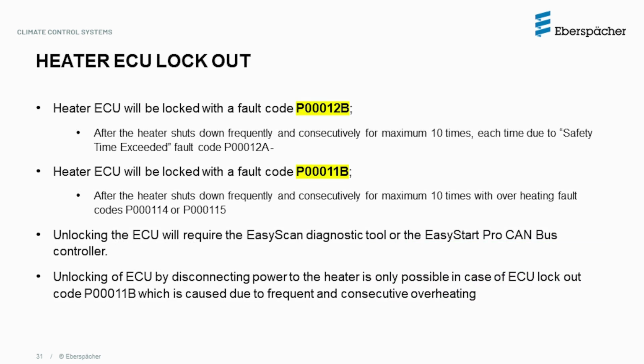An ECU lockout fault code will be triggered after 10 consecutive failure to start faults or after 10 consecutive overheat faults. The ECU lockout codes are P00012B for frequent failure to start faults and P00011B for the frequent overheat faults. The preferred way to unlock the heater would be to reset the lockout counter back to 0 using the Easy Scan diagnostic tool. This will retain all the fault codes and the fault code data, which could be used to analyze heater issues in the future.